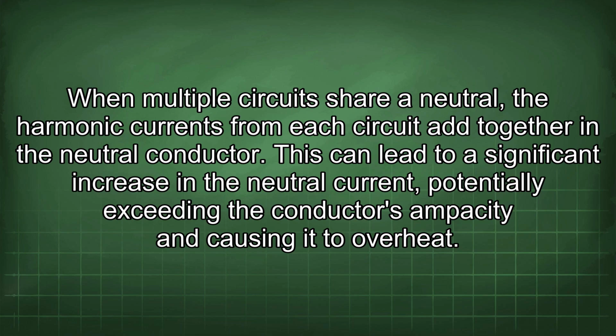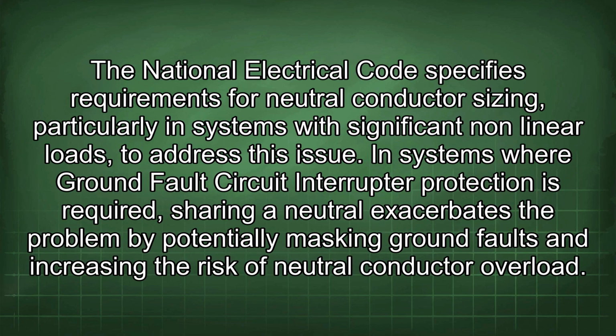When multiple circuits share a neutral, the harmonic currents from each circuit add together in the neutral conductor. This can lead to a significant increase in the neutral current, potentially exceeding the conductor's ampacity and causing it to overheat. The National Electrical Code specifies requirements for neutral conductor sizing, particularly in systems with significant nonlinear loads, to address this issue. In systems where ground fault circuit interrupter protection is required, sharing a neutral exacerbates the problem by potentially masking ground faults and increasing the risk of neutral conductor overload.